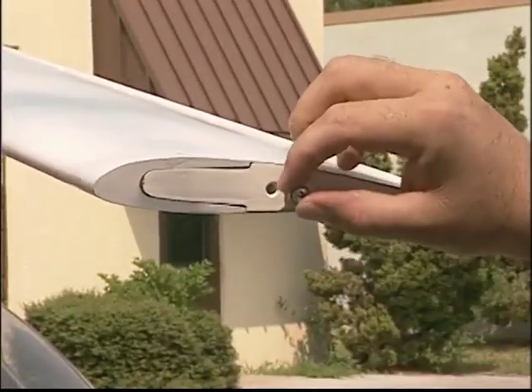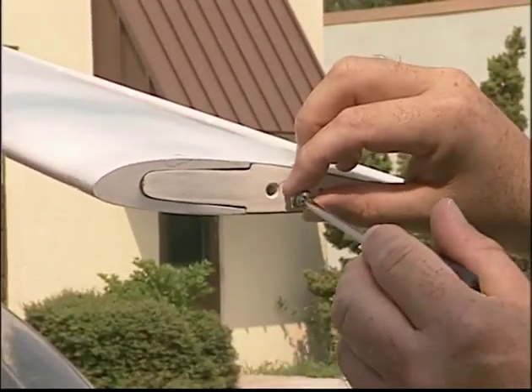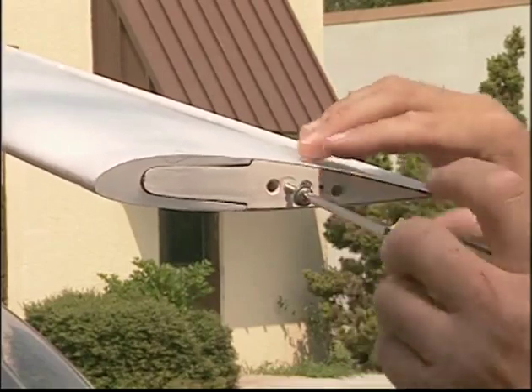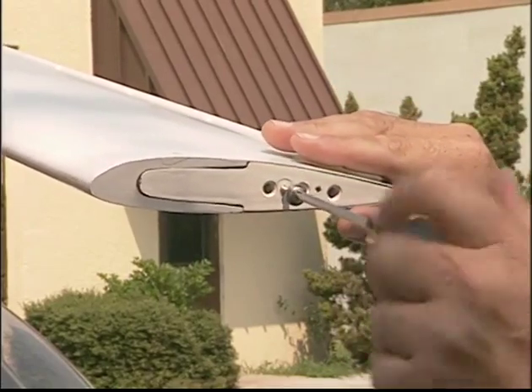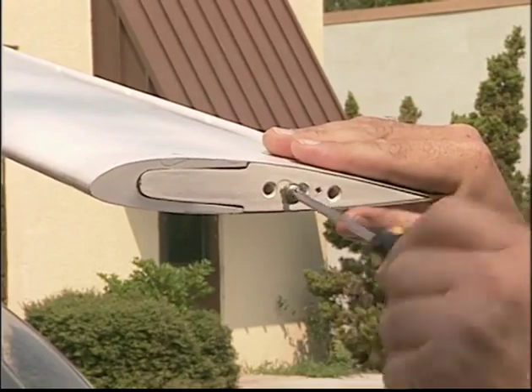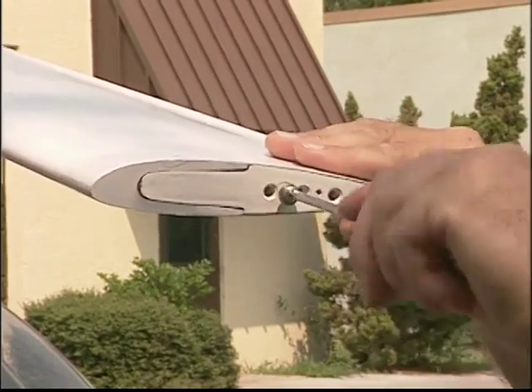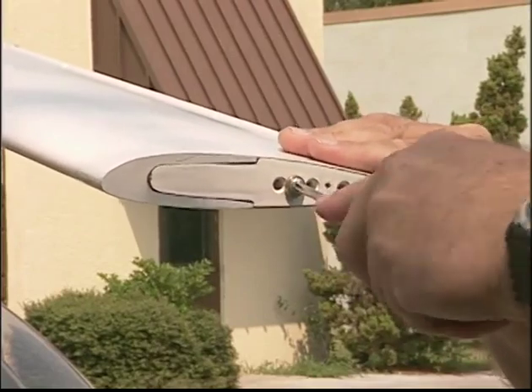If the system is out of balance, adding a number 8 screw 3/4 inches long with a 3/16 inch regular washer to the end of one blade will take care of the problem, provided, of course, weight is the problem. And you may need to remove the screw from that end and add it to the other end to get the weight on the correct blade.